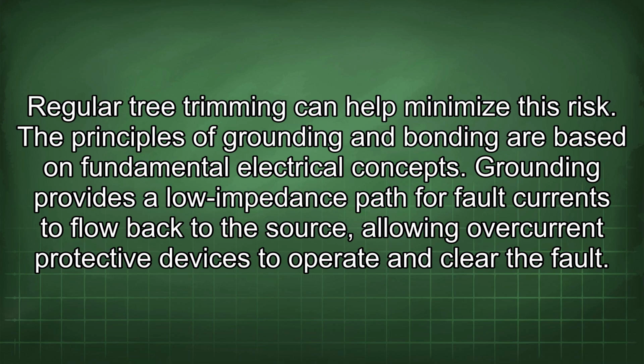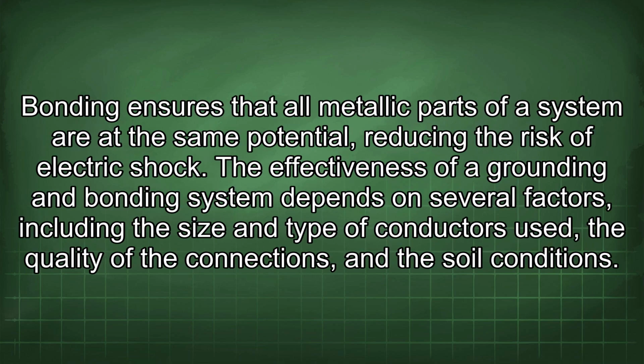The principles of grounding and bonding are based on fundamental electrical concepts. Grounding provides a low impedance path for fault currents to flow back to the source, allowing overcurrent protective devices to operate and clear the fault. Bonding ensures that all metallic parts of a system are at the same potential, reducing the risk of electric shock.